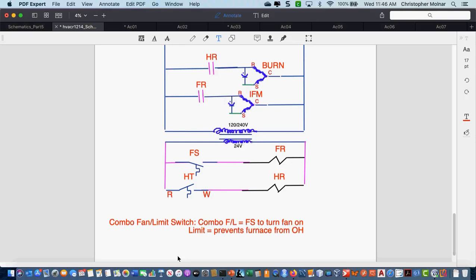That's a repair. It's a frequent one. But even more frequent goes along with your lack of indoor airflow. What's another reason why you might not have enough air through that furnace? Incorrect duct size. Yeah, let's think simpler. Think way simpler. Clogged filter. I go on about 10 or 20 of those calls every winter, and down here every summer. It's awesome to do a $150 service call and then charge $25 extra for the filter. Clogged filter is by far the most frequent cause of a furnace overheating.